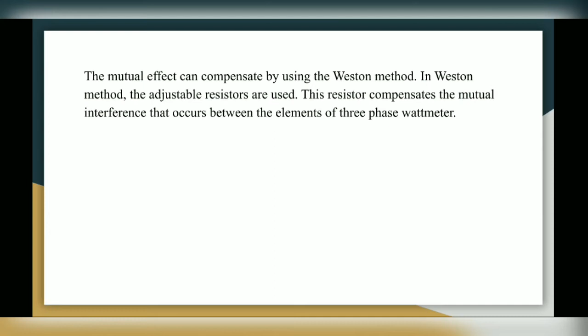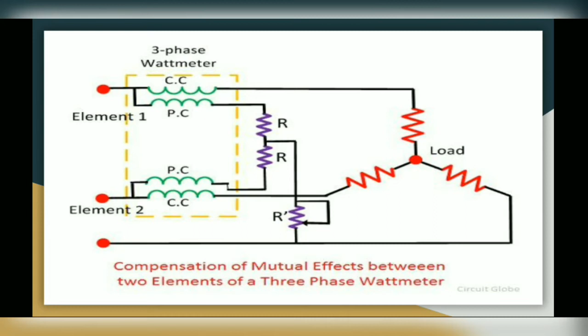The mutual effect can be compensated by using the Weston method. In the Weston method, adjustable resistors are used. This resistor compensates the mutual interference that occurs between the elements of the three-phase wattmeter. So by using the iron shield you can avoid this error, and by using the Weston method, that is, by using adjustable resistors, you can also avoid this error. In this diagram you can see resistors are connected to avoid this mutual interference error.